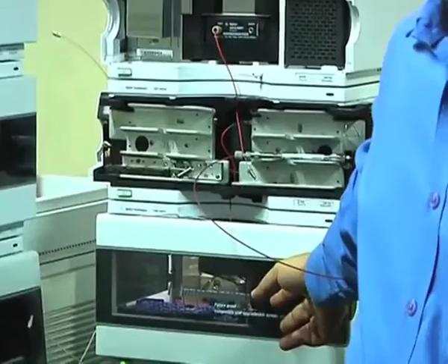Then you have an autosampler. If you recollect my slide where I said it can be automated, you can put hundreds of samples in that. You define your runs, and you can carry out your other work, and by the time your analysis gets over, it's automated. But what I mean to say here is, if you put 100 samples and the run time or separation time is 30 minutes, let us say, by the time the 100th sample comes, it is 300 minutes, isn't it? Or more than that. What it means is samples might degrade by the time their number comes. So to maintain a constant temperature, you have a thermostat. You maintain the temperature of the samples in the autosampler at 4 degrees, so that your sample doesn't degrade during the analysis, if you are running the automated type of analysis.